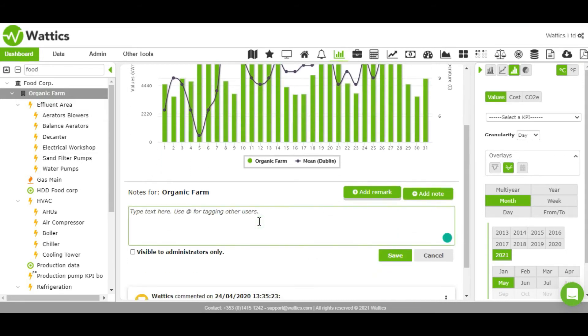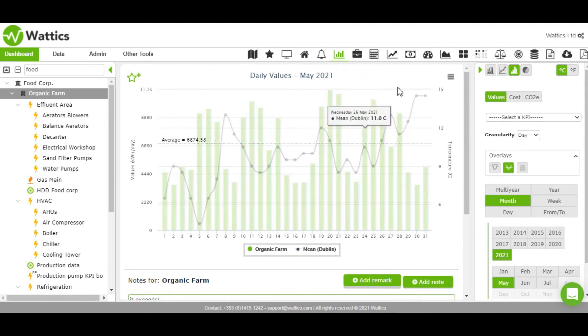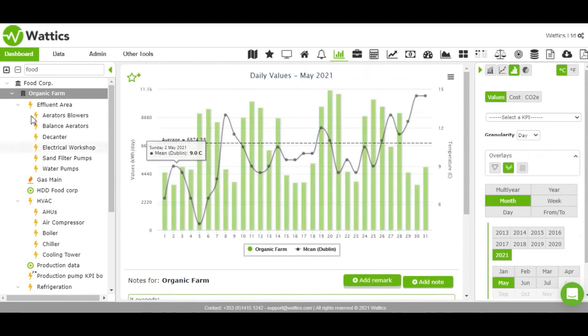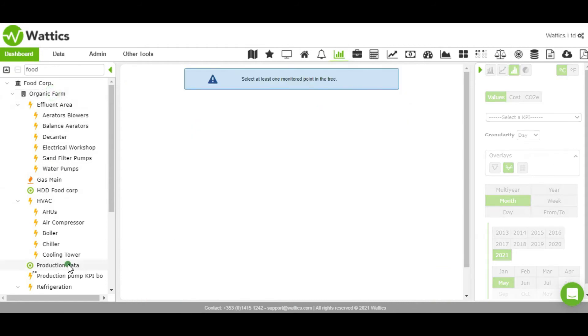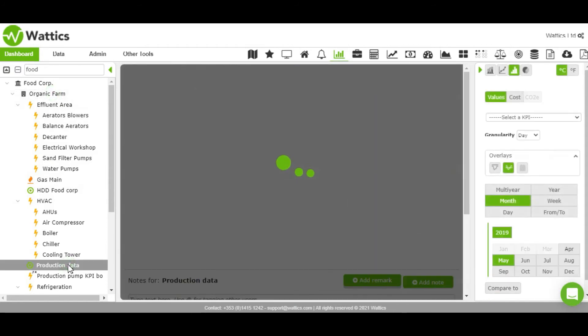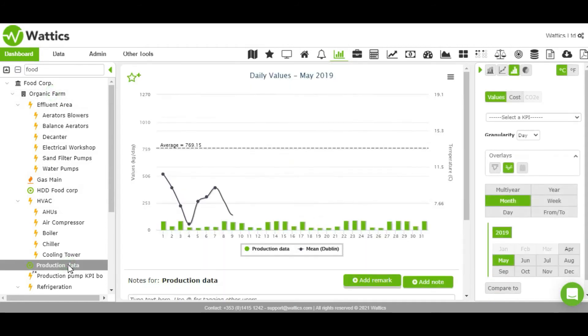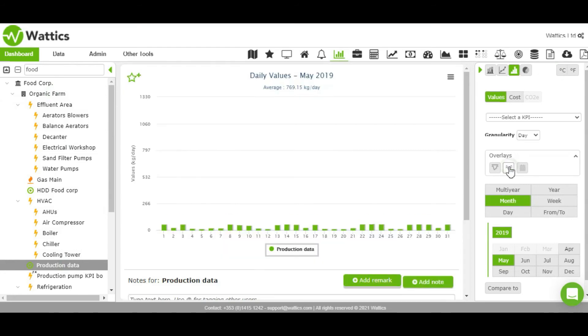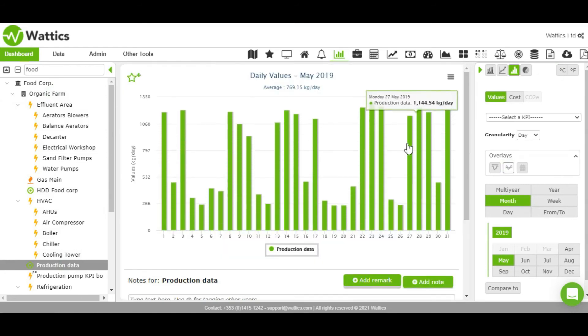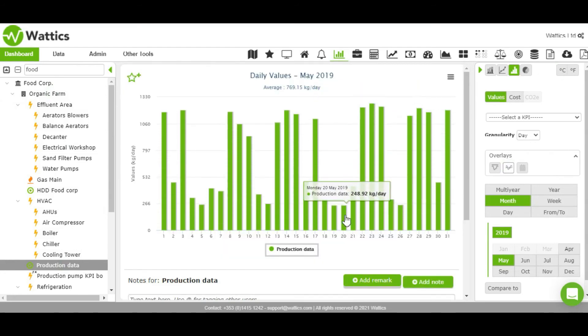Another useful application of the breakdown tab is to normalize the consumption by energy performance indicators such as the production, capacity, or square footage. If production or sales are increased, then adjusting the data in terms of consumption per tons of food processed will make sense of the associated increase in energy consumption.